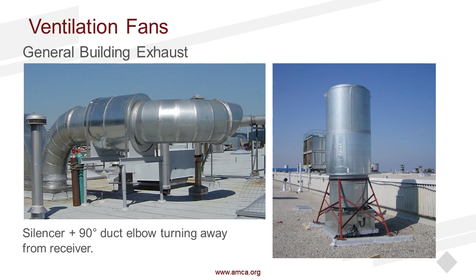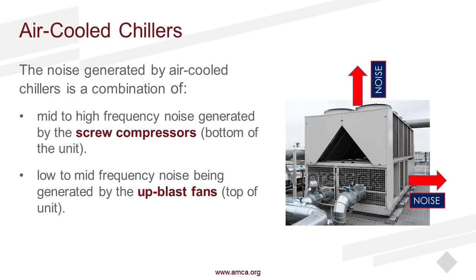Air-cooled chillers. We talked about that. We've been talking about it for a while over the years, but it's a 2 noise source system. You have the compressors down below, and you have the noise propagating from the upblast fans. And it's really interesting. You have mid to high frequency noise on the screw compressors, low to mid frequency on the upblast fans, and sometimes all the way over to the 8,000 hertz. But a lot of people will try to do one or the other. They'll try to usually put wraps, and you've seen wraps on the compressors. And that's really good, but it's a 2 noise source system, and it may not do enough.